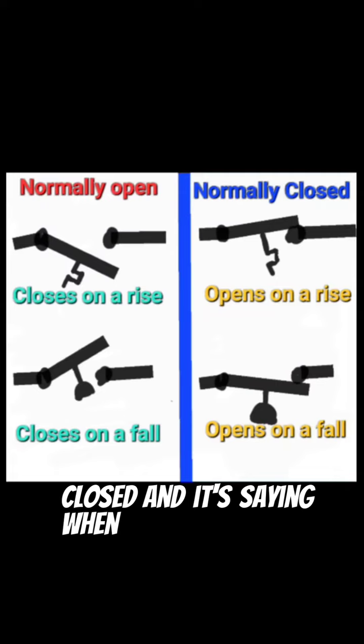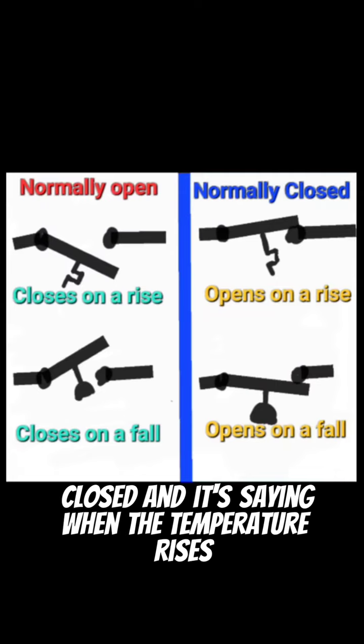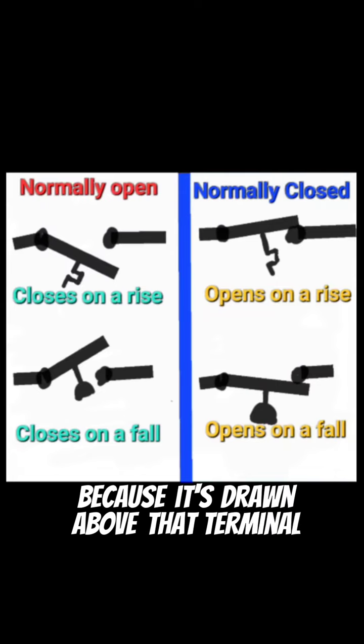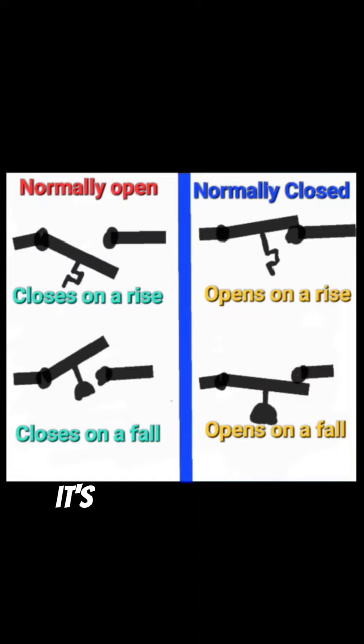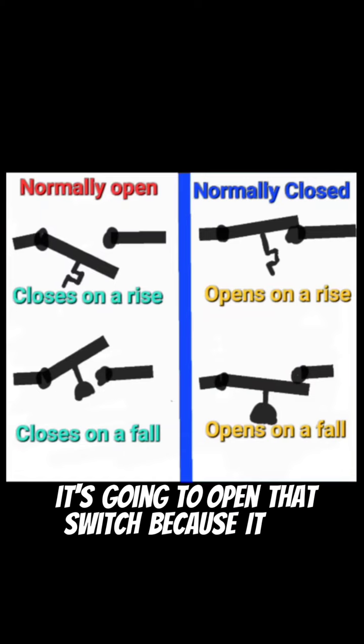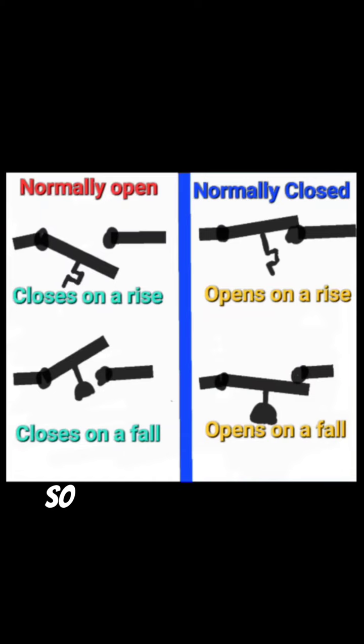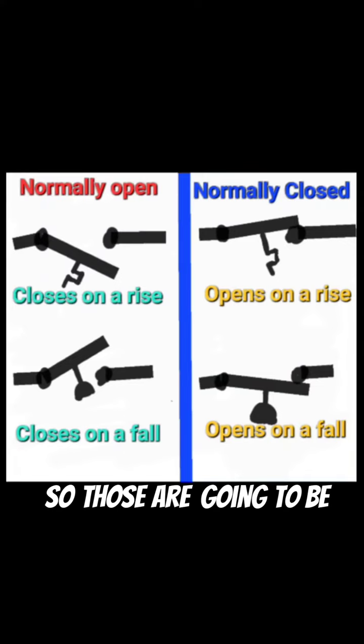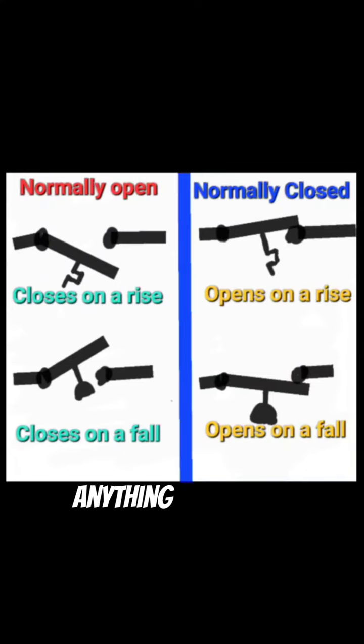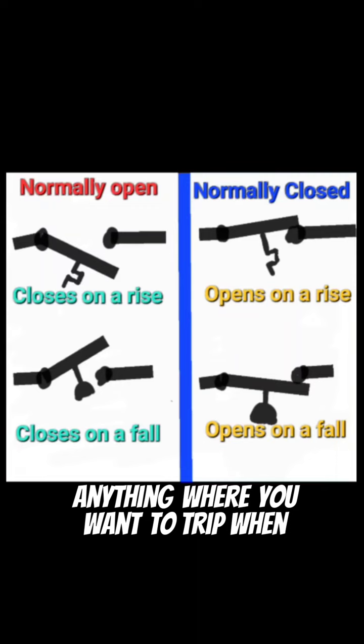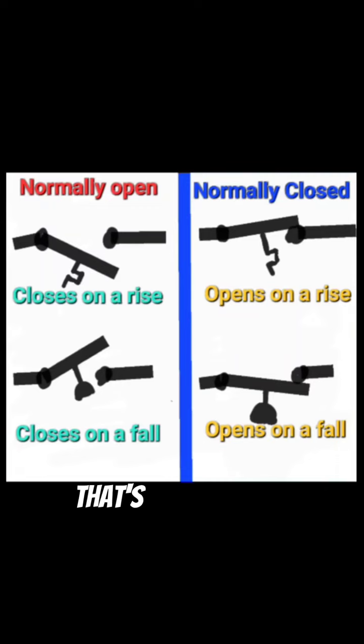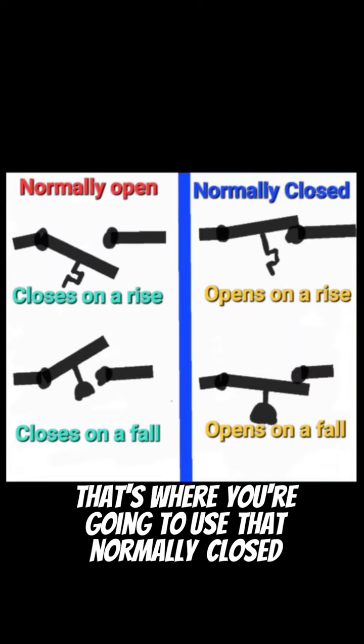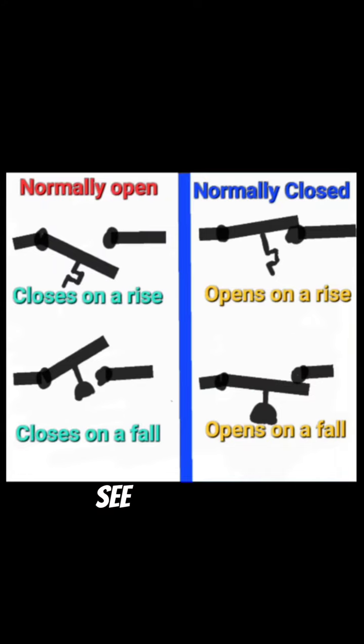And it's saying when the temperature rises, because it's drawn above that terminal, it's going to open that switch because it can only open up, right? So those are going to be kind of like your high limits. Anything where you want to trip when the temperature increases, that's where you're going to use that normally closed open on a rise. That's where you're going to see that symbol.